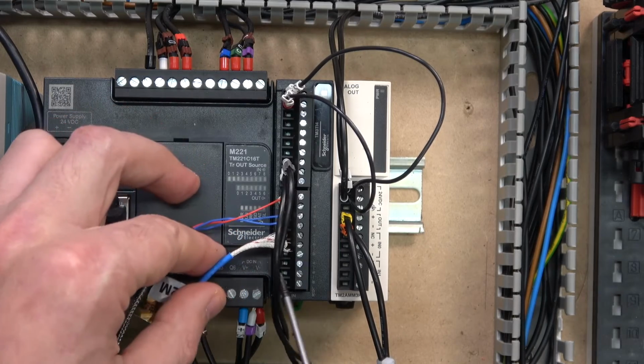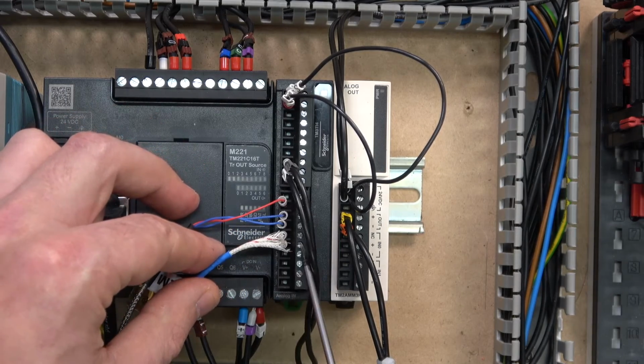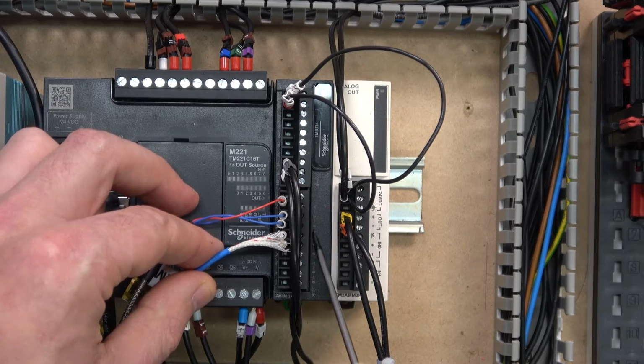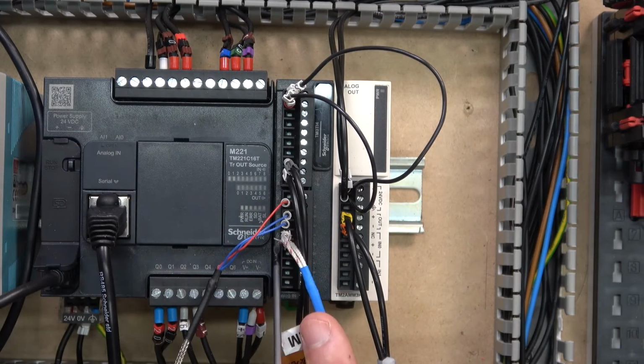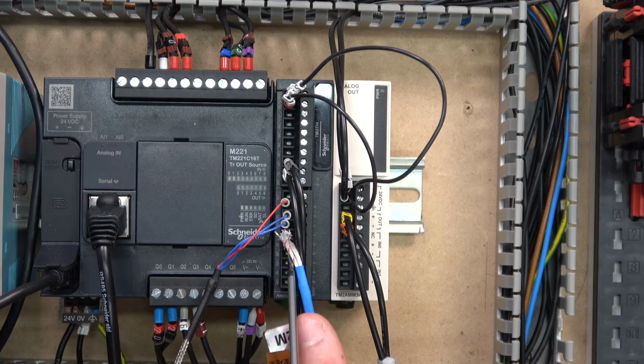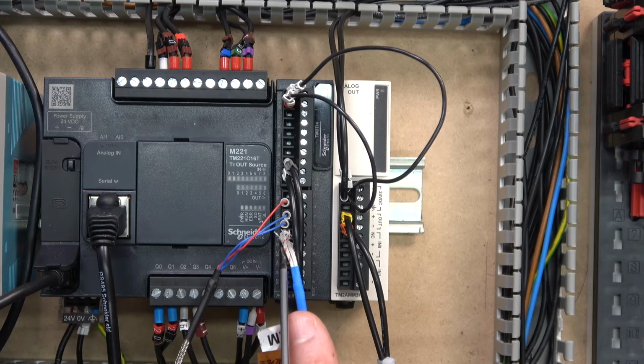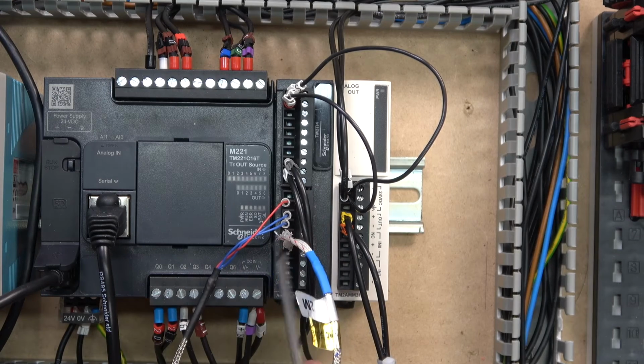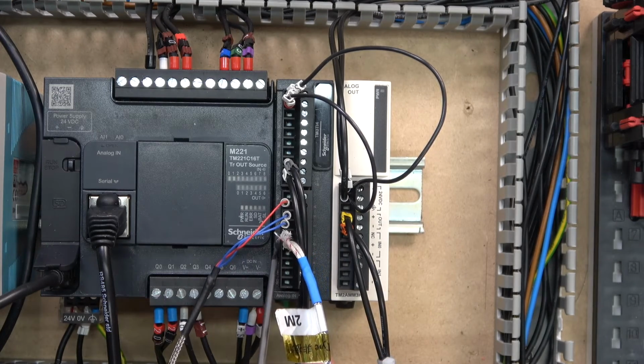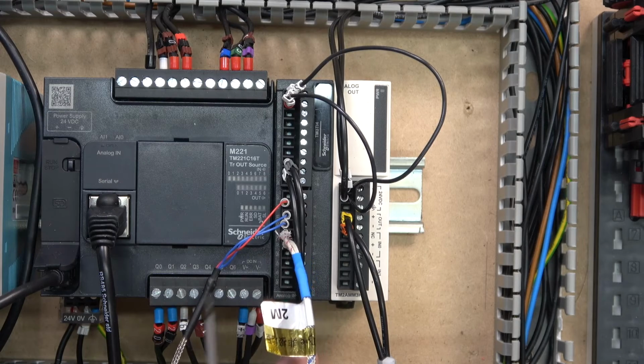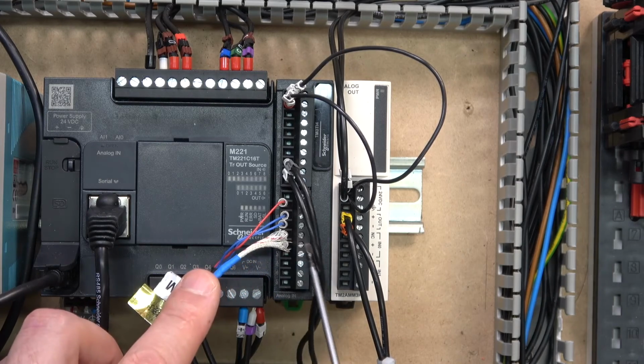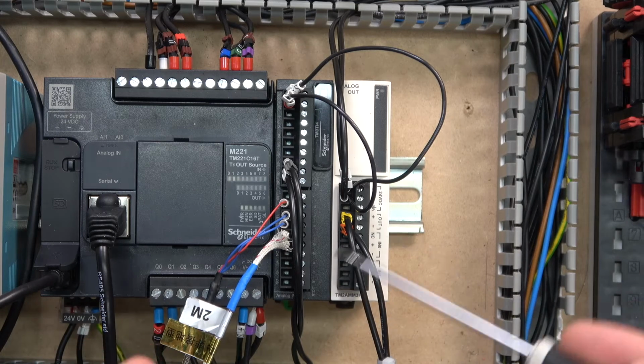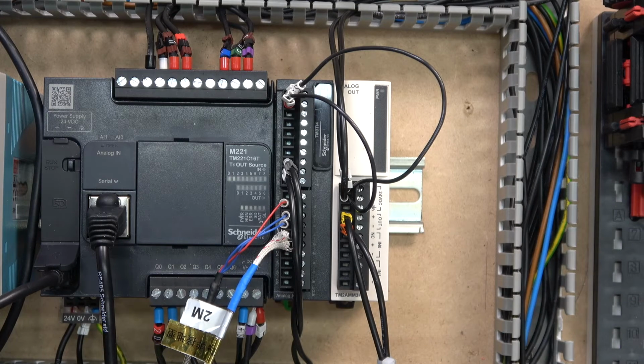When it comes to TC type thermocouples, you ignore this side of it. It's just, as you can see in here, a plus and a minus. In my case, the plus for my thermocouple is marked with a red line on it. That will go into I2 plus, and my uncolored one is going to be I2 minus. That's pretty much it. The thermocouple is wired in, and all you need to do is go into the configurations and set it all up. That's exactly what we're going to do now. Let's jump on the laptop and have a look at it.